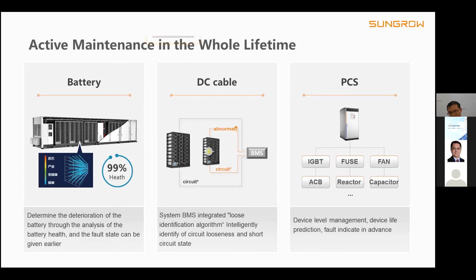The last part is about the PCS - all key components inside the PCS are monitored in real time. This means the IGBT, the ACB, the fan, the fuse, and the reactor are all monitored in real time. So if there are any problems or failures, we will know, and the system will give out a potential cause. Then we can arrange people, judge and determine the issue, and send people to site to do repair work or replacement to save maintenance time. So this is our active maintenance.